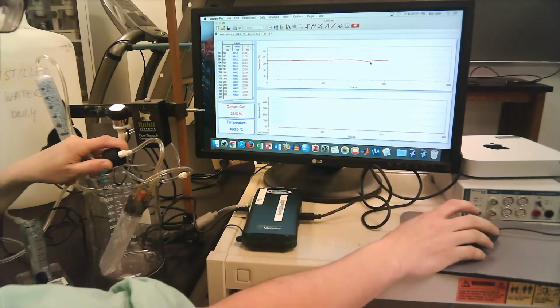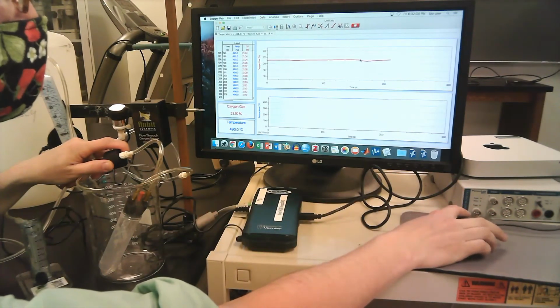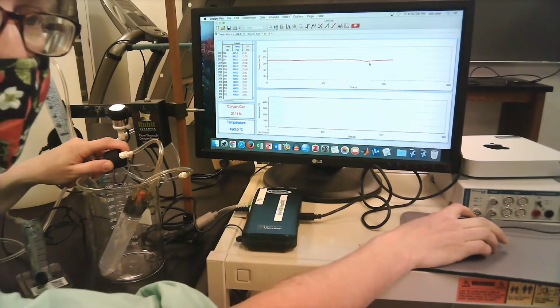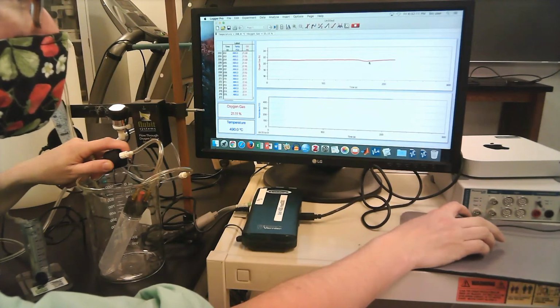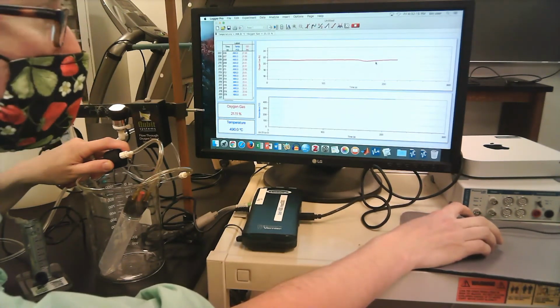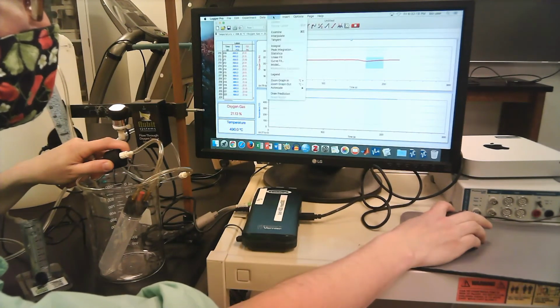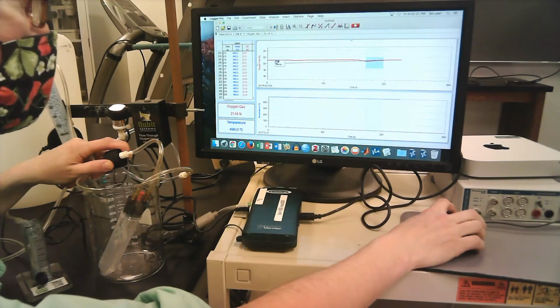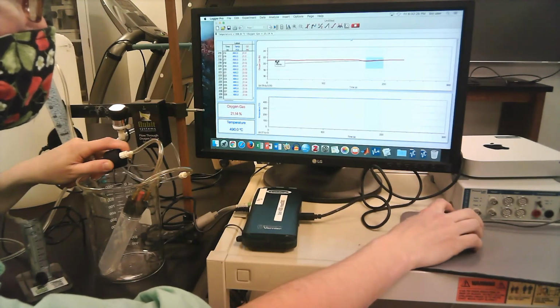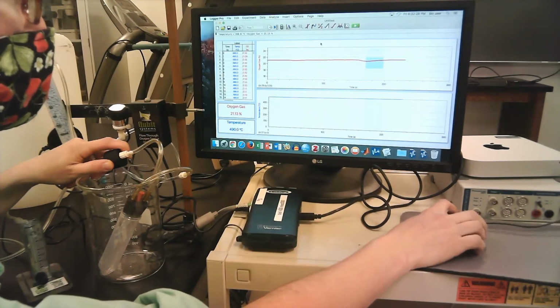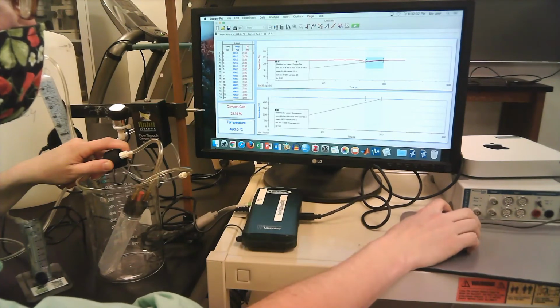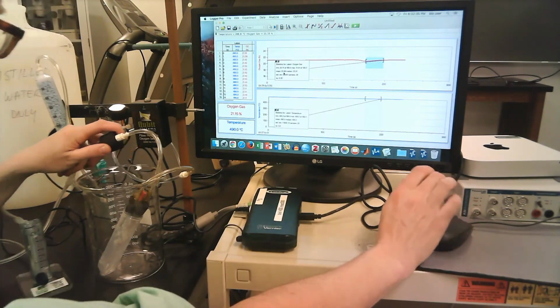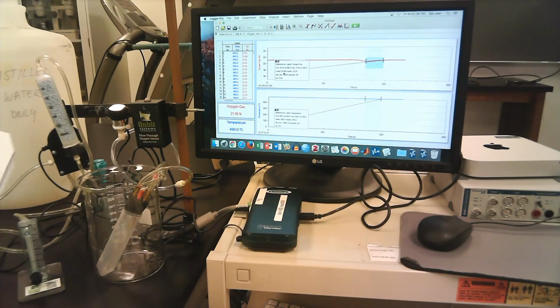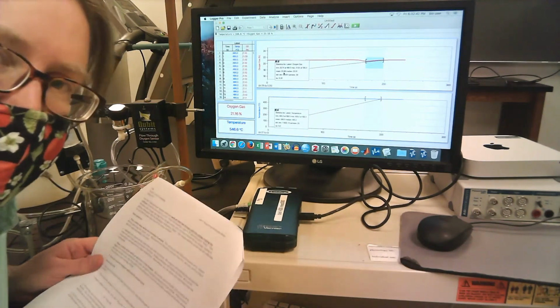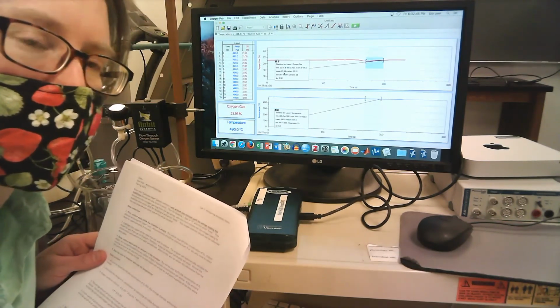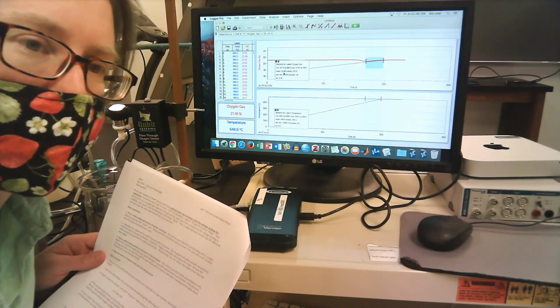And so when you actually have an animal in the chamber, you should see a period where the oxygen concentration goes down. And then what you want to look for is, once again, a relatively flat and stable portion of your reading. And you just want to do the same thing: Analyze, Statistics, and calculate the mean. Since this is still running, it's going to wait until I stop. So now I can do Analyze, Statistics, and there's the mean for that section of my recording. In the event that the temperature probes misbehave, we can also record temperature just using one of the BAT thermocouple probes instead.